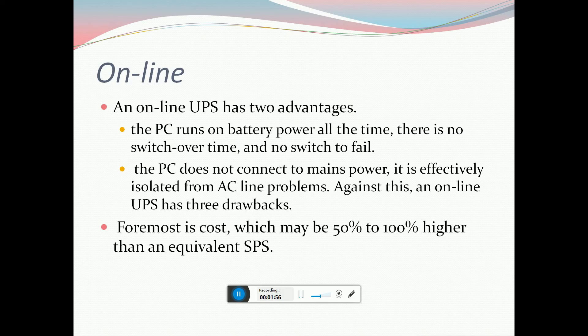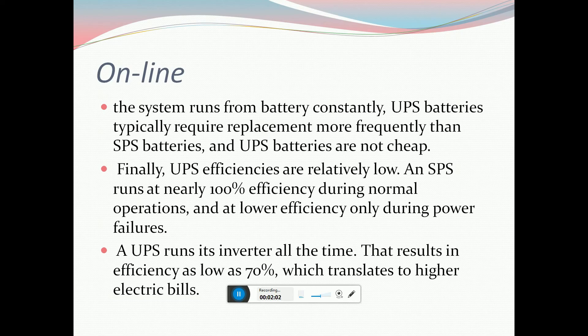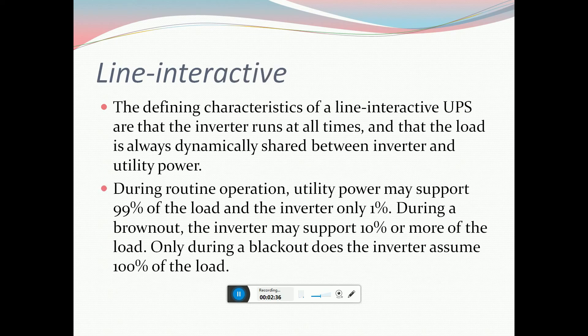Online UPSs have three drawbacks. First, cost is maybe 50% to 100% higher than an equivalent SPS. Second, since the system runs from battery constantly, UPS batteries require replacement more frequently than SPS batteries, and UPS batteries are not cheap. Finally, UPS efficiency is relatively low — while an SPS runs near 100% efficiency during normal operation, the online UPS runs at an efficiency as low as 70%, resulting in higher electricity bills.